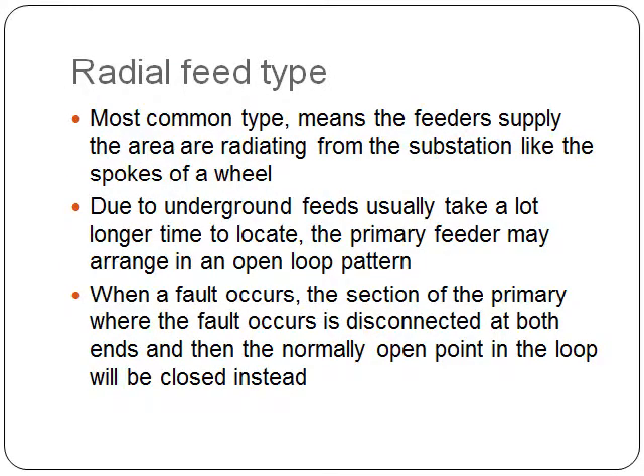For underground residential distribution, it is mostly using the radial feed type. This means the feeders supply the area radiating from the substation like the spokes of a wheel. Due to underground faults usually taking a lot longer time to locate, the primary feeder may also be arranged in an open loop pattern. When a fault occurs, the section of the primary where the fault occurs is disconnected at both ends and the normally open point of that open loop will be closed instead, so that services can be continually fed while isolating the fault that needs to be investigated.